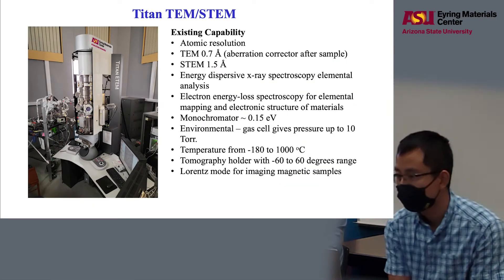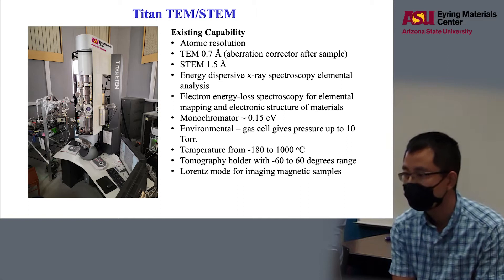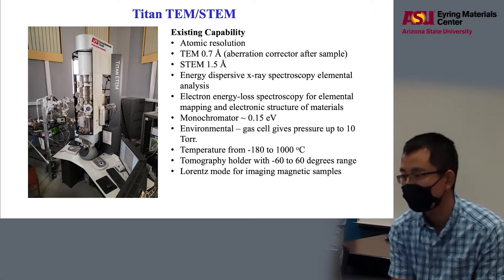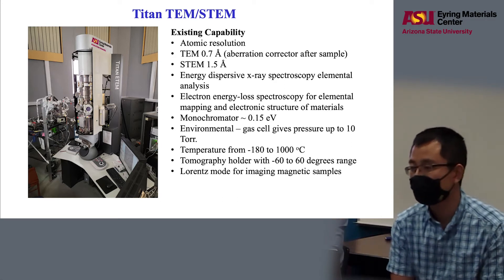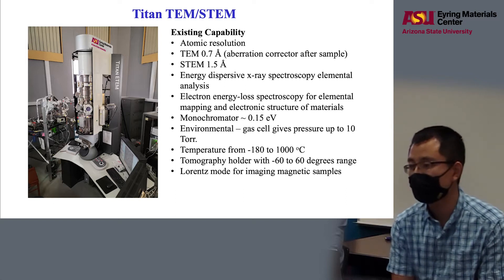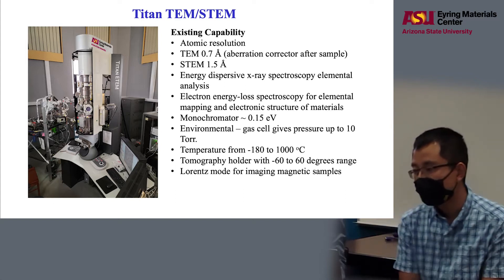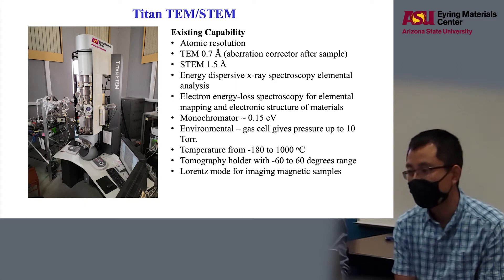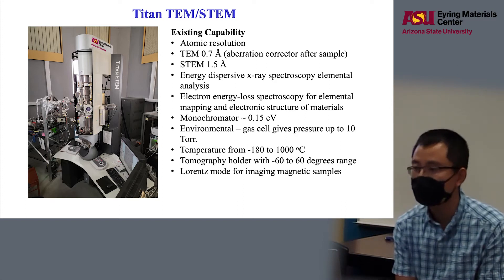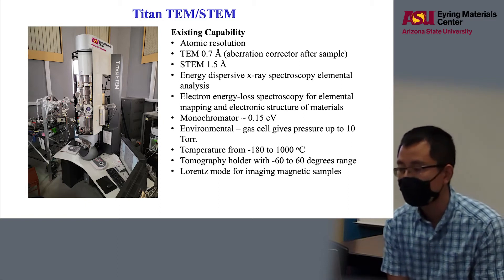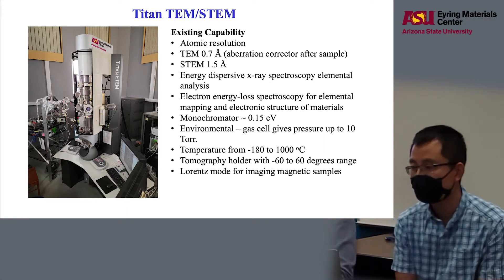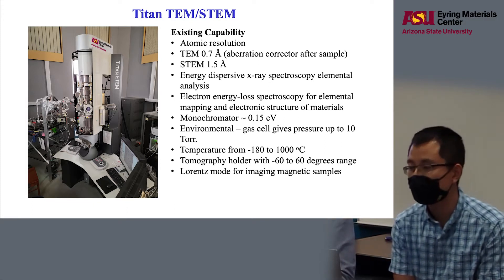First, I want to quickly review the existing capabilities. This microscope provides atomic resolution. For TEM mode, it provides 0.7 angstrom spatial or information limit, and for STEM, it provides about 1.5 angstrom. It has an energy dispersive X-ray spectrometer for elemental analysis. And with the new EELS detector and spectrometer, we can also do fast mapping using EELS. This microscope also has a monochromator, which can provide energy resolution down to 0.15 eV.